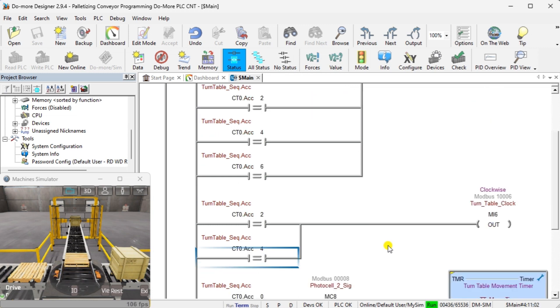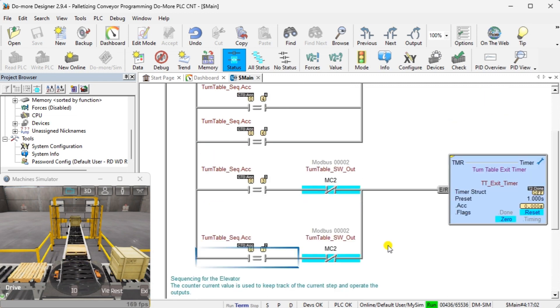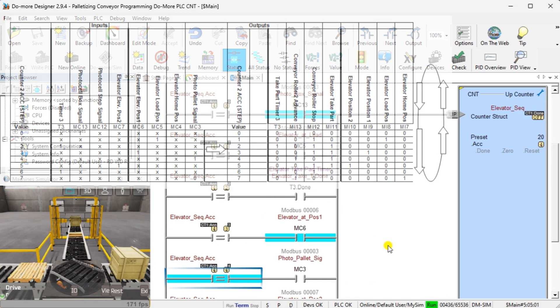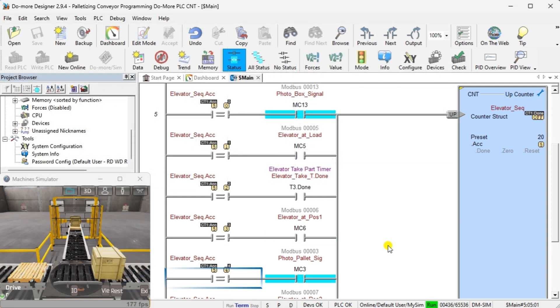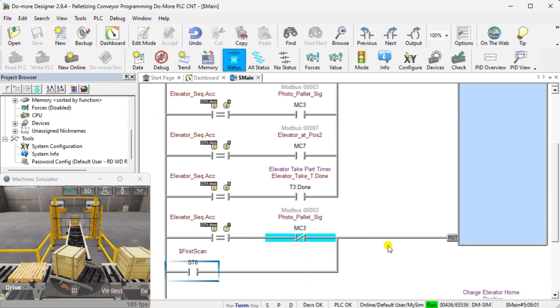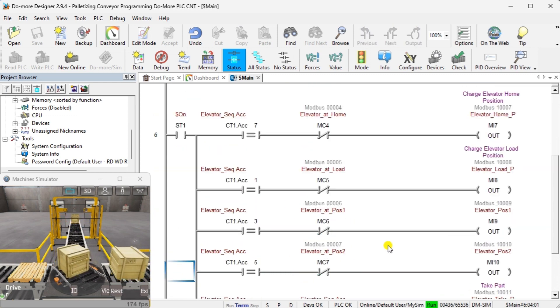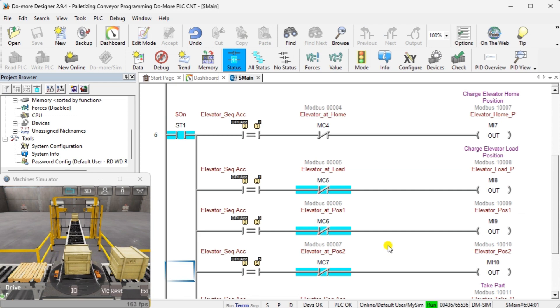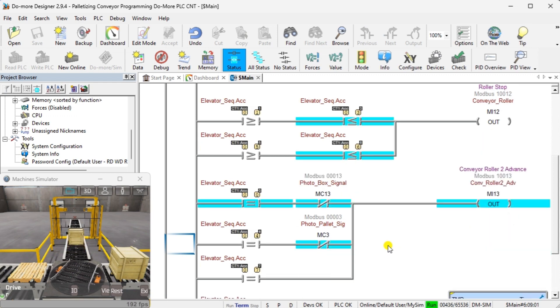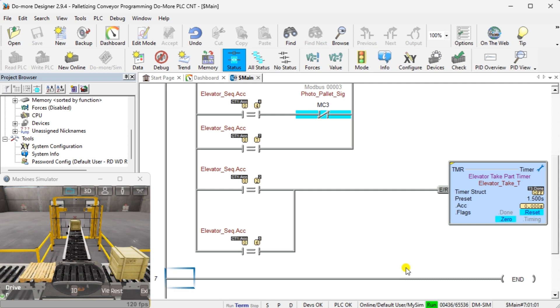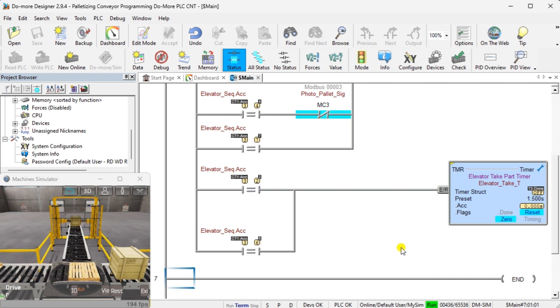This is counter 2, which controls the elevator sequence. Returning to the sequence table, you can see the steps and inputs that will advance or increment the counter. Here are the outputs of the elevator sequencer. You can see the counter value and inputs that will activate each output. If the output is to be turned on with more than one counter value, the conditions are placed in parallel. This is the end of the ladder logic code. Download the DoMore program to the DoMore PLC simulator and ensure that the simulator is in run mode.